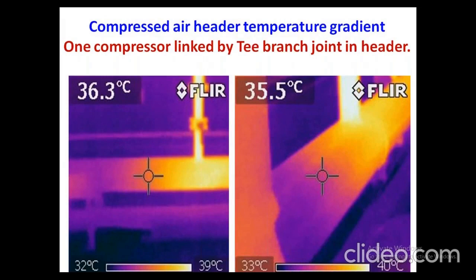We have been using this infrared thermal imager for more than 10 years during our energy audits. We use it in the compressor house. You can see on the left image, this is a 3000 CFM compressor delivering at the header, and that is a 2000 CFM compressor. See, the 2000 CFM compressor is at a higher pressure. This is not allowing the 3000 CFM flow to go in. You need to have conjoining bends. With this thermal imager, we were able to see this, and we suggested it, and immediately they changed from this T connection to 45 degree conjoining bends. Automatically the pressure drop problem was solved, and the cut-in cut-out also improved for the given compressor.